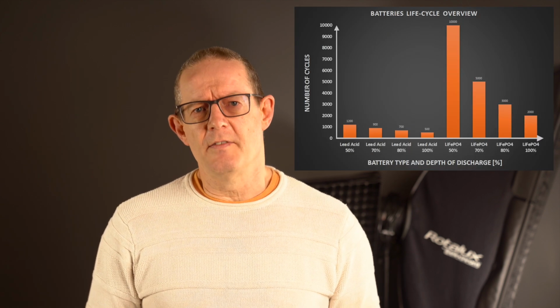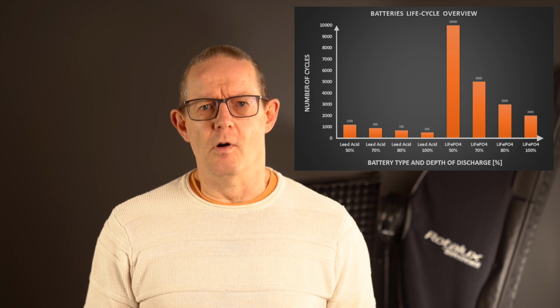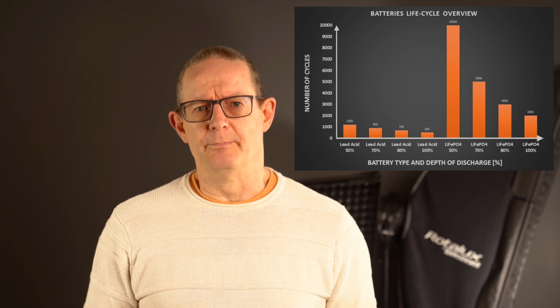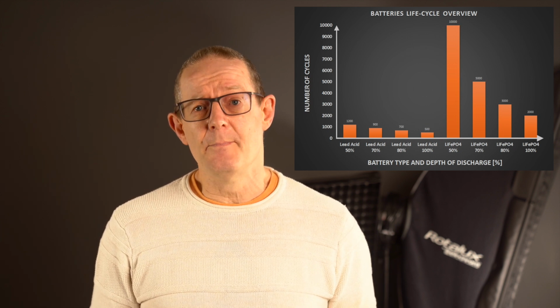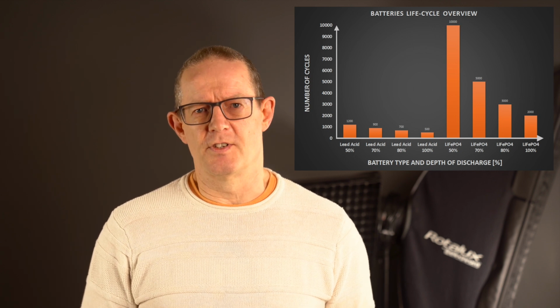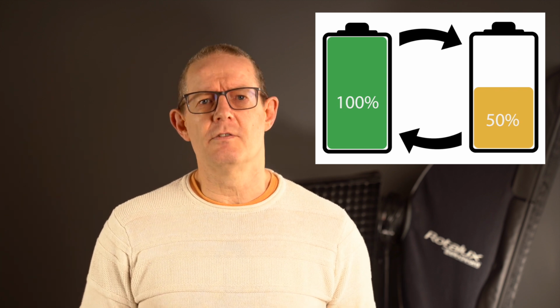Check the number of life cycles the battery will perform and still be in warranty - some are unlimited, others are 6,000 cycles. Check the depth of discharge - how much energy can you use from the battery before it needs to be recharged? Some can provide 100% depth of discharge, DOD, whilst others are limited to 80 or 90%.